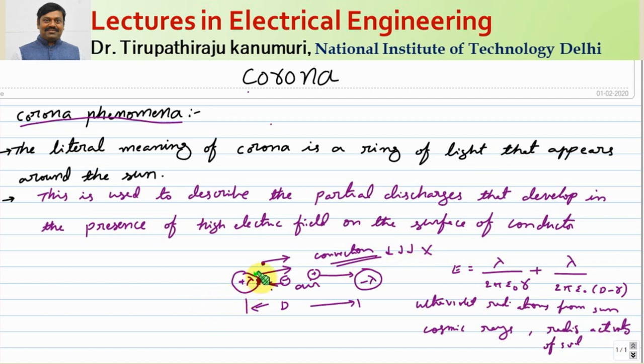If the voltage is increased such that the electric field intensity at the surface of the conductor exceeds 30 kV per centimeter (peak), or 21.2 kV RMS, the air will start breaking down. This means the charged particles already present — through which convection current flows — acquire sufficient energy and start accelerating at a faster rate, bombarding neighboring atoms.